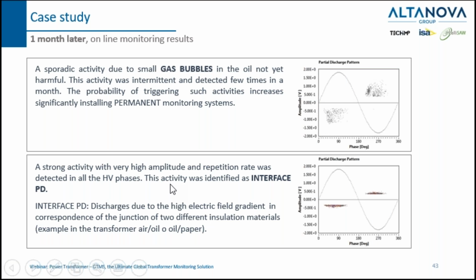After almost 1 month of monitoring, we found two different types of PD. The first one was related to gas bubbles, so PD not so harmful in the oil. And the second was an interface PD. Interface PD is a type of discharge due to the high electric field gradient, which occurs at the junction of two materials with different electric strength, for example the interface between air and oil or oil and paper.